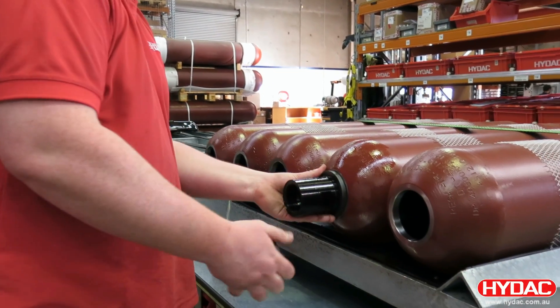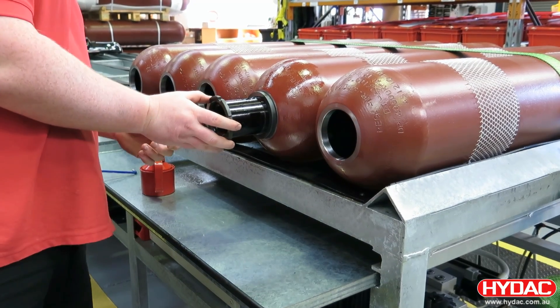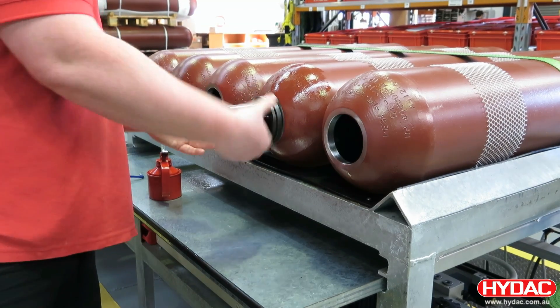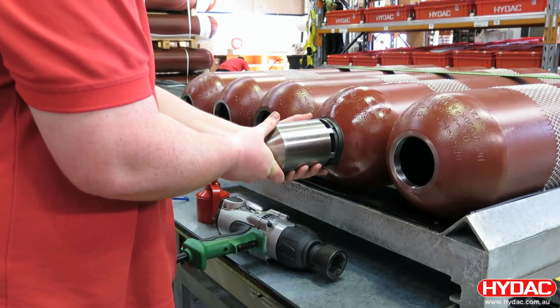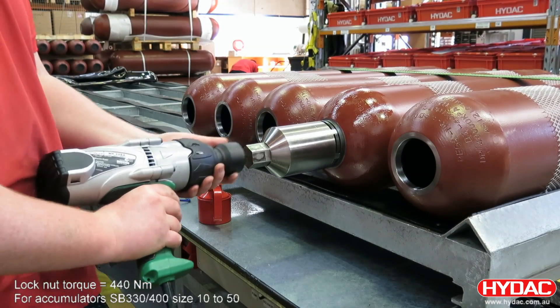The fluid port assembly is pulled up by using a lock nut against a spacer. The lock nut has a chamfer on it — this is facing towards the shell. The nuts normally tighten down using a C spanner and a hammer. As this is a production environment for us, we use a specially prepared socket.